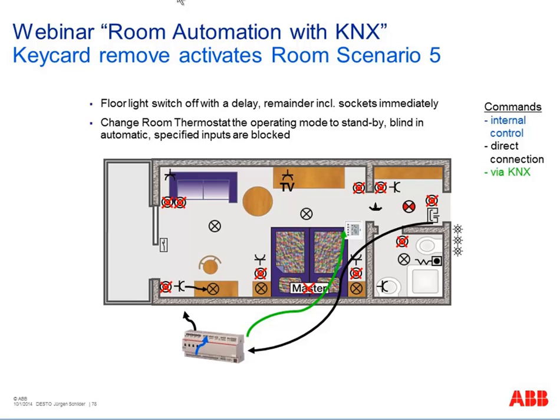Good, or here a small overview, the next room scenario. Maybe you leave the hotel room, then you have directly connected to a binary input the key card reader, so we remove our key card, send information to the room master. The room master is doing some internal linked features, for example, he switches off the light here on the desk light, all other lights, but after some seconds he calls the second event and switches off this light.